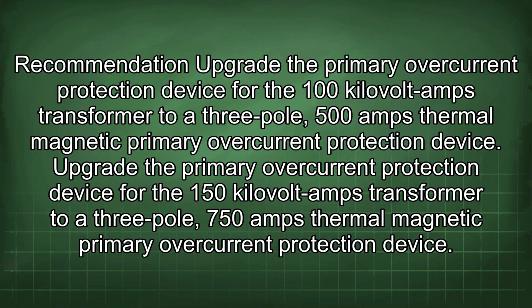Recommendation: upgrade the primary overcurrent protection device for the 100 kilovolt-amps transformer to a 3-pole 500 amps thermal magnetic primary overcurrent protection device. Upgrade the primary overcurrent protection device for the 150 kilovolt-amps transformer to a 3-pole 750 amps thermal magnetic primary overcurrent protection device.